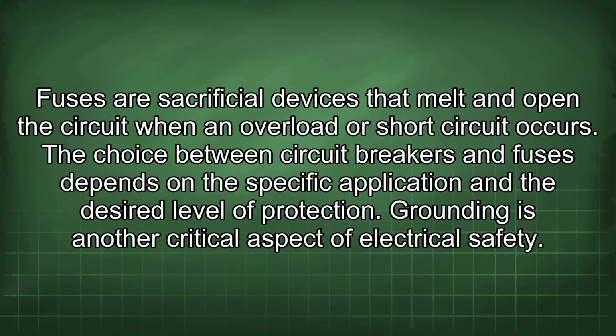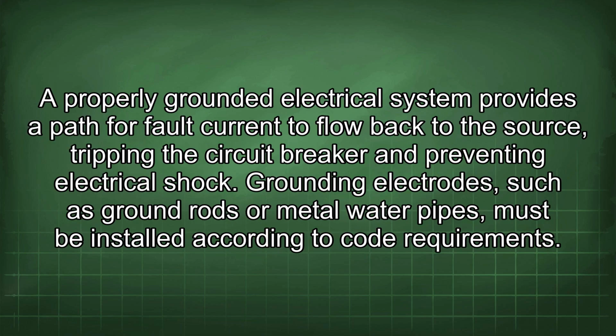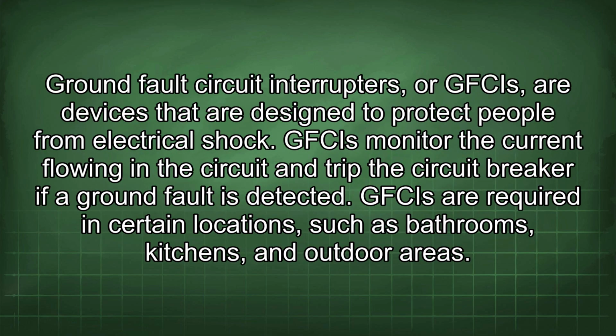Grounding is another critical aspect of electrical safety. A properly grounded electrical system provides a path for fault current to flow back to the source, tripping the circuit breaker and preventing electrical shock. Grounding electrodes, such as ground rods or metal water pipes, must be installed according to code requirements. Ground fault circuit interrupters, or GFCIs, are devices that are designed to protect people from electrical shock. GFCIs monitor the current flowing in the circuit and trip the circuit breaker if a ground fault is detected. GFCIs are required in certain locations such as bathrooms, kitchens, and outdoor areas.